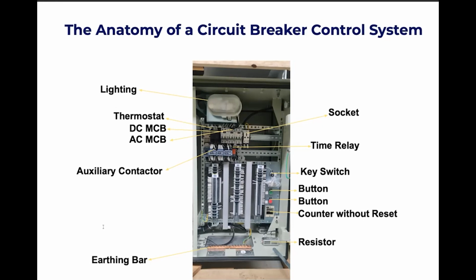Continue from the auxiliary contactor. Basically, here, as a function to add more context for controlling the operation of the circuit breaker, an auxiliary contactor is employed in the control circuit. Here we use both Siemens auxiliary contactors, which have the manufacturer labels 3RH6140 1BF40 and 3RH2911 1GA04. In contrast, the 3RH2911 1GA04 has a specification of 1 pole for an auxiliary contactor, and the 3RH6140 1BF40 has 3 poles and 40 ampere.